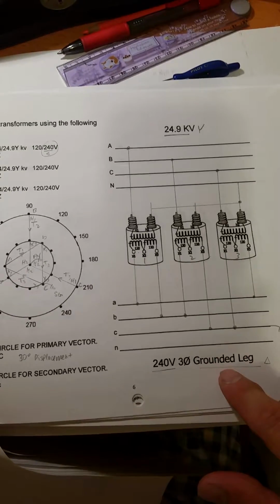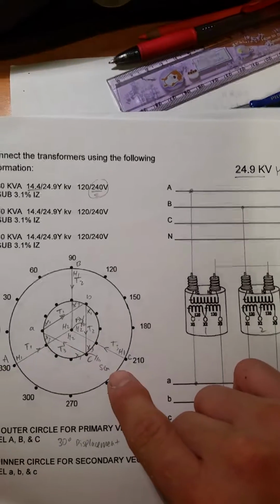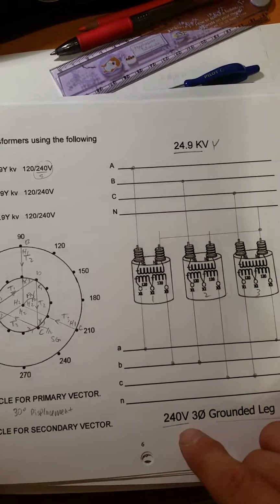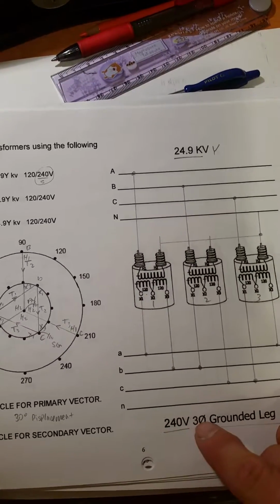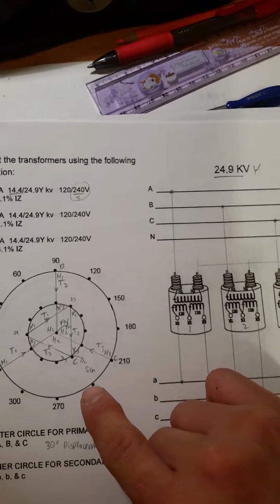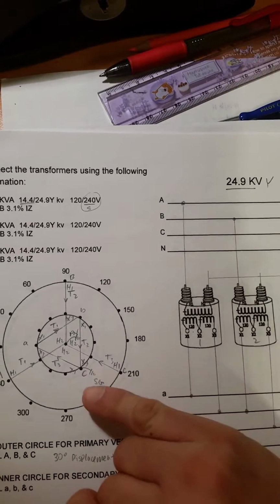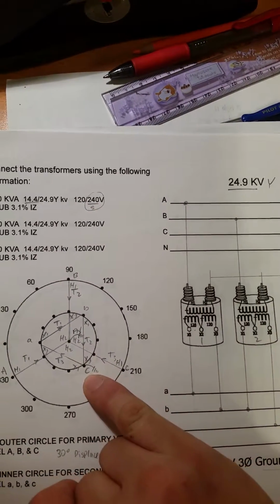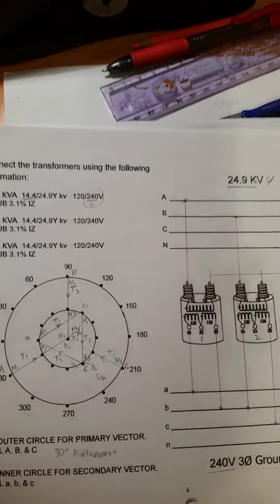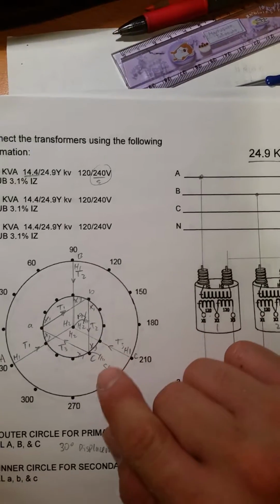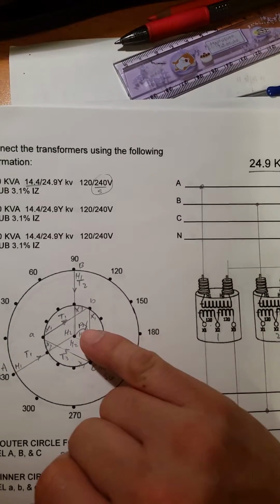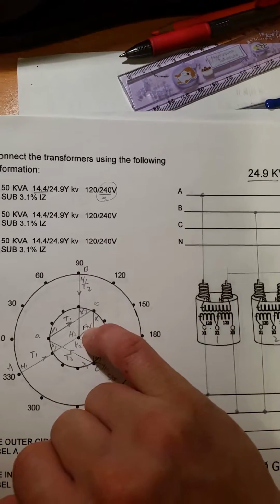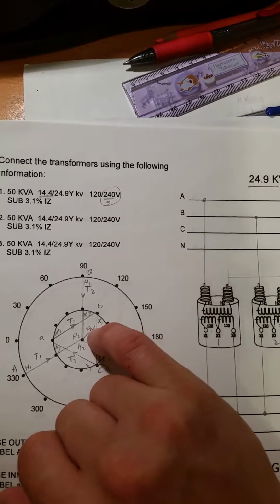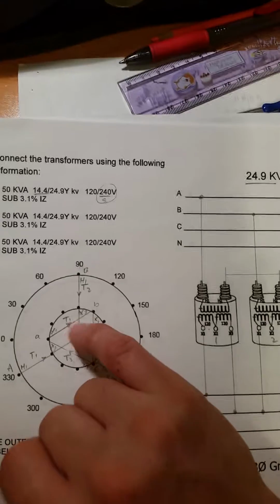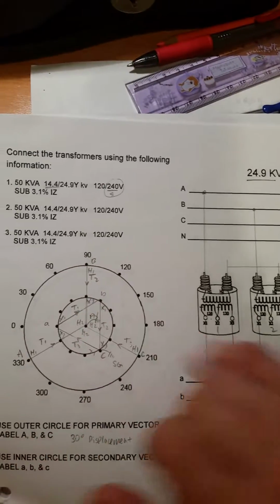Okay, grounded leg, that's the one I told you on the secondary side. It says 240 three phase grounded leg, so I grounded C phase. Okay, I did put SG secondary ground, and then your primary, I put PN for primary neutral, but it should be PG primary ground. Always your Y, you always want to ground it. Okay, so that's how I did that one.